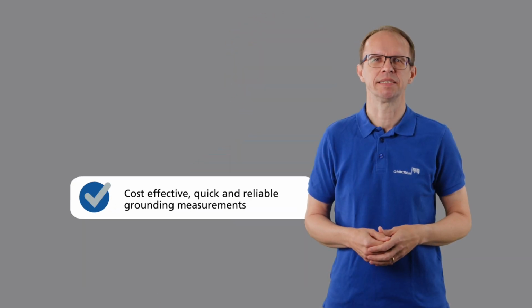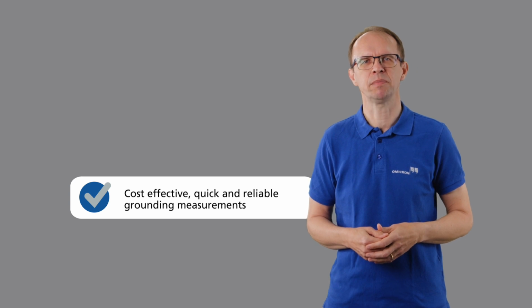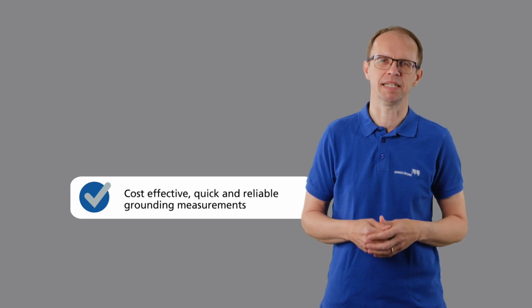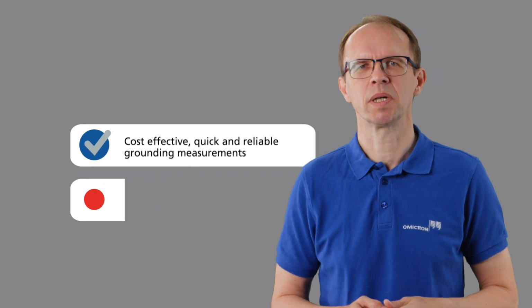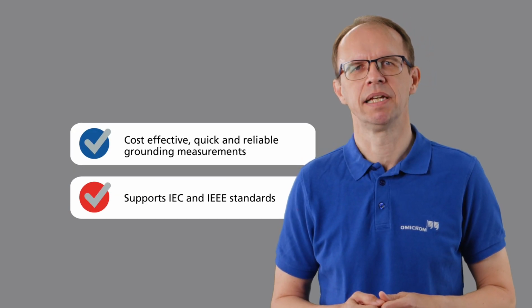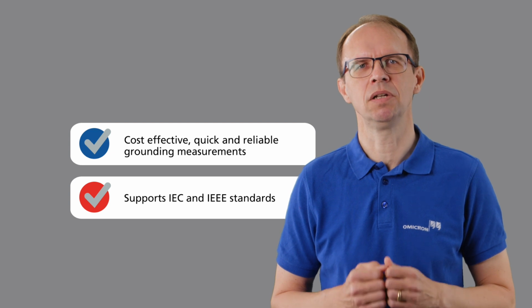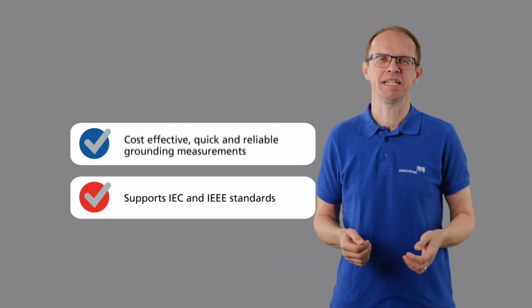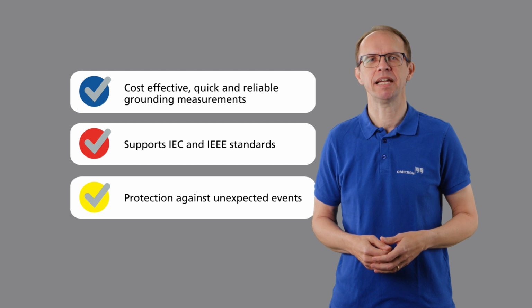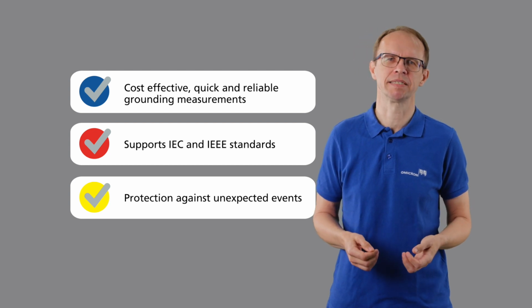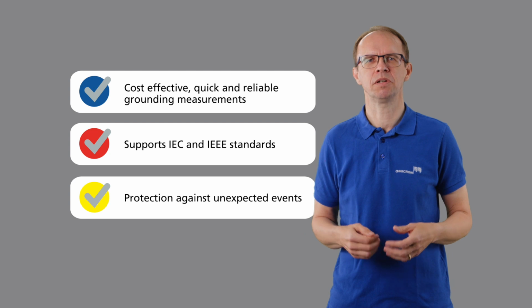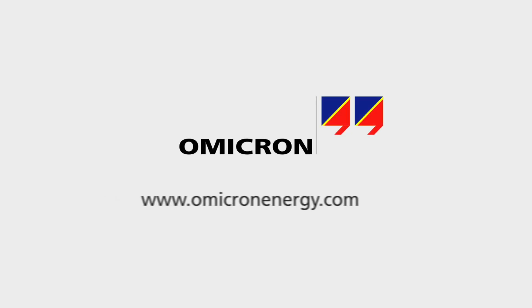So to sum up, here are 3 things to keep in mind. With CPC 100 and CPCU1, measuring ground impedance is cost-effective, fast and reliable. We support IEC and IEEE standard-compliant measurements, including reporting. Our test system protects against unexpected events like dangerous voltage spikes and line fault currents up to 30,000 amperes. For more details, visit our website or contact us directly.